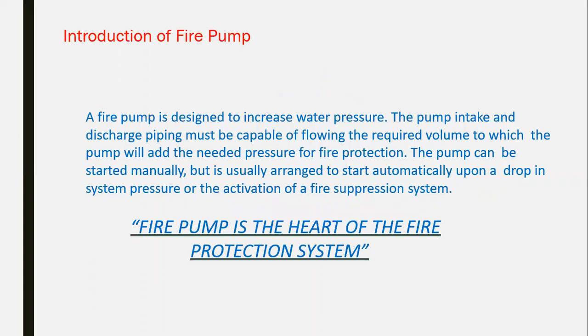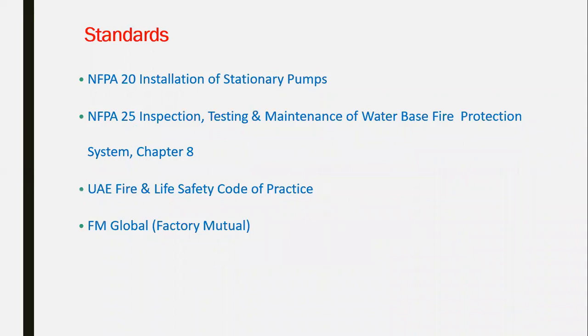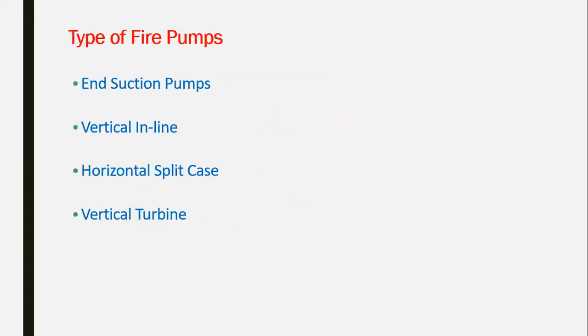Okay. As we said, the fire pump is the heart of the fire protection system. All other systems work with the firefighting, starting from the standpipe and landing valve, hose reels, the sprinklers and the pipes, control valve, etc. All of these are accessories or devices associated with the fire pump, which is the heart of our firefighting system. The main standards applicable for this testing are NFPA 20, which is the installation of stationary pumps, NFPA 25, which is the inspection, testing, and maintenance for the water-based and life safety sections, and FM Global, Factory Mutual.